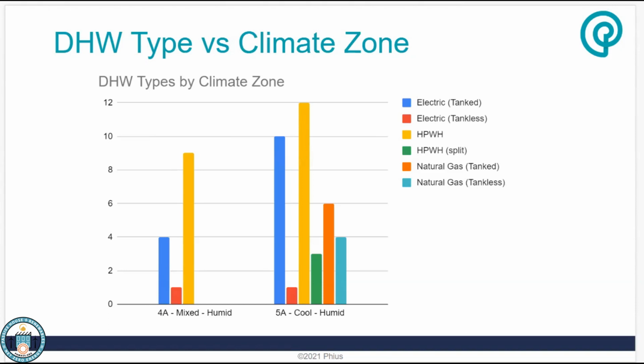You need to provide capacity in the electric panel. You need to provide that, so when that system is retired in 15, 20 years, or whenever it's at the end of its lifespan, you're fully ready to bring in a new electric version of that device. So that's why we have natural gas tanked and natural gas tankless on this list, that's the orange and the teal color.